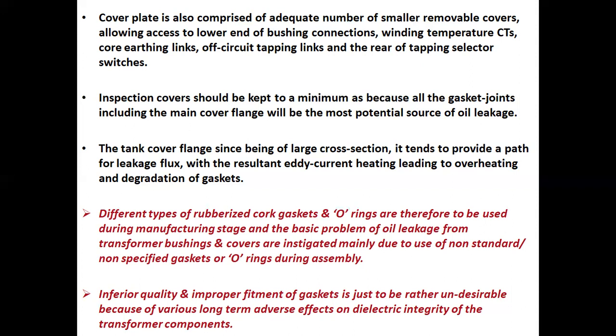Different types of rubberized cork gaskets and O-rings are therefore to be used during the manufacturing stage, and the basic problem of oil leakage from transformer bushings and covers is instigated mainly due to the use of non-standard or non-specified gaskets or O-rings during assembly. Another point to be noted: inferior quality and improper fitment of gaskets is undesirable because of various long-term adverse effects on the dielectric integrity of the transformer components.